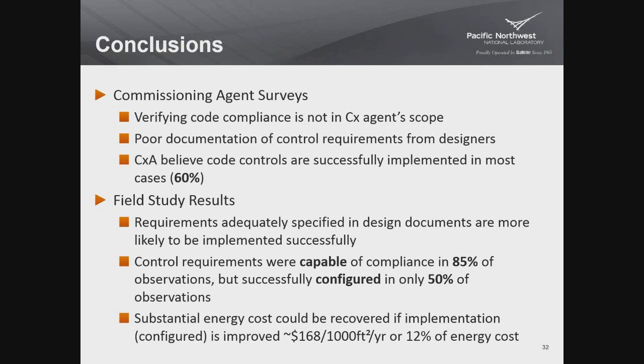So that tells us with very little investment, we could close this gap. These controls, since they're capable of providing these energy saving sequences, these energy saving strategies, we could move this up closer to the 85% with very little investment. And then finally, substantial energy cost savings could be recovered if there was better implementation of the code requirements. Approximately $168 per 1,000 square feet per year, or 12% of the total energy cost.